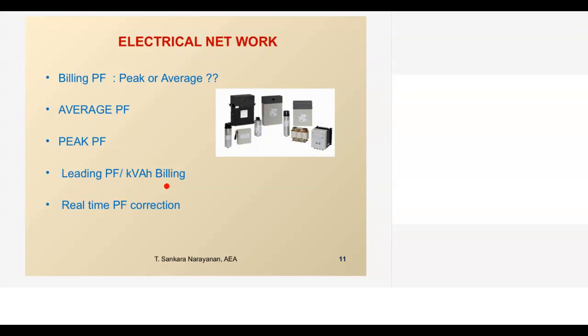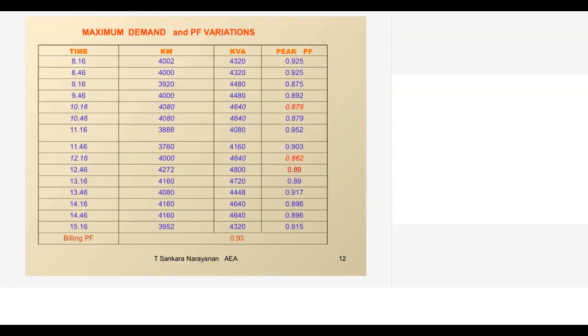Slowly they are shifting to kVAh billing. When kVAh billing is there, there is no separate column for power factor. Directly, whatever is the kVAh registered, that will be billed for you. So whoever is shifting to kVAh billing, the end consumer has to clearly monitor how the PF is maintained. In some of the states where kVAh billing is already done, if there is a leading power factor, the incentive component is reduced. So today we have to go for real-time PF correction wherever kVAh billing is there and leading power factor is very strictly monitored. This is a condition, again, to know the peak power factor.